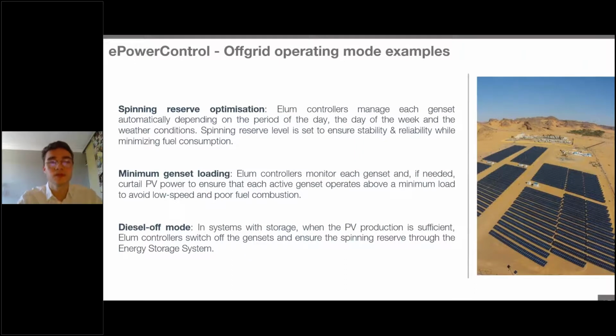So what are the different features of the power control on off-grid configuration? First of all, you have this spinning reserve optimization. Basically it's being able to turn on or off different power units to ensure that those different set points are configured, that we are using the BESS properly to ensure there is no loss in PV production.